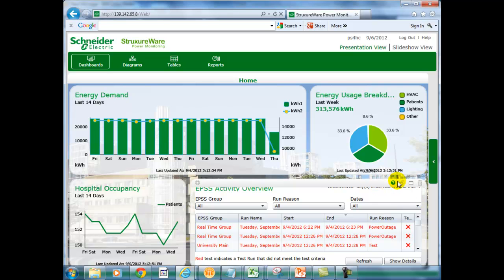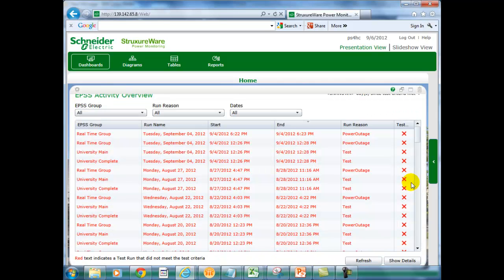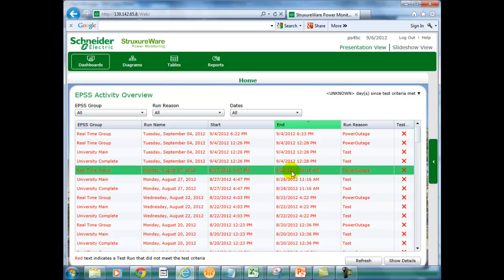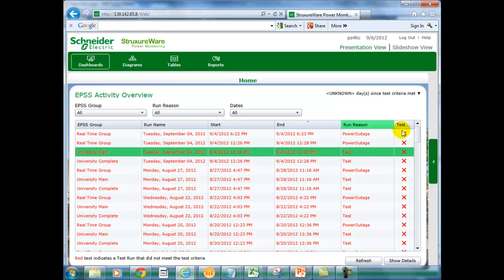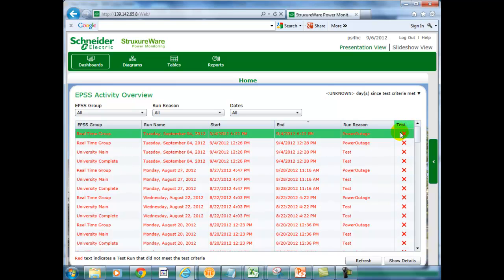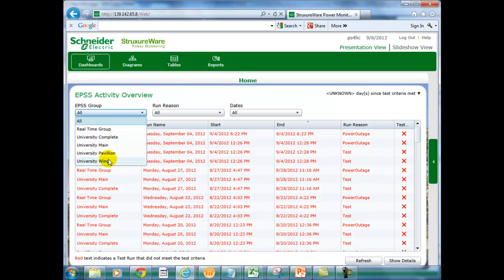Let me maximize this gadget so we can see it clearly. So here's the pass-fail indication. The criteria for pass-fail is specified in the configuration and includes things like tolerance times for transfer switch operation. You can also organize your test equipment in different groups. Here we have about 5 groups tied to different locations in the facility, each of which have their own generators and transfer switches. Looks like we have an awful test record here. Pretty much everything has failed. But this is for demo purposes, so tolerances are set pretty tight.